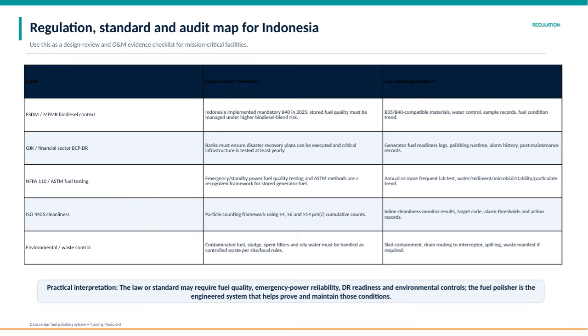The ISO 4406 standard addresses cleanliness in terms of particle counting, focusing on particles of certain sizes. This is monitored with inline cleanliness devices, setting target codes and alarm thresholds, and recording any required actions to maintain optimal fuel purity.